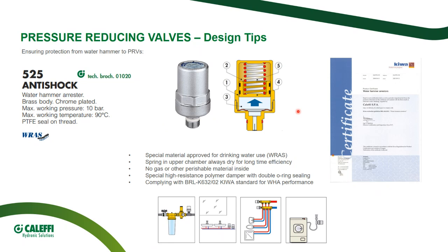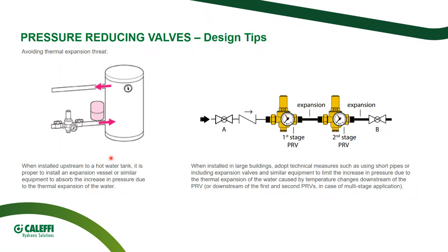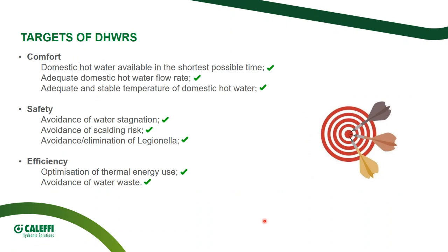Also, the performance of these devices is better confirmed and certified by a third party, and Caleffi has this, complying with a KIWA entity. Always consider the thermal expansion caused by the temperature increase, so evaluate the installation of expansion tanks throughout the system, and also consider the expansion of the water in case of multi-staging reduction between primary and secondary device. Now, let's go back to our table of targets, and we see that every one of them has been reached with some care in the technical details of sizing, installation, and positioning of the device.